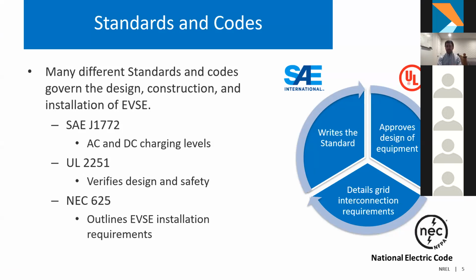That's the standard that's written that it's very common for EVSE to comply with. And then there's the Underwriters Laboratory, which actually approves that design and makes sure that it's designed and manufactured in a safe manner. So everything is designed safely for the user and the grid as well. But what we're going to focus on is actually the National Electric Code and NEC section 625. And this actually outlines installation requirements. So it ensures that the grid is still operating safely for the electric vehicle, and the EVSE itself is not going to cause any undue burden on the grid.